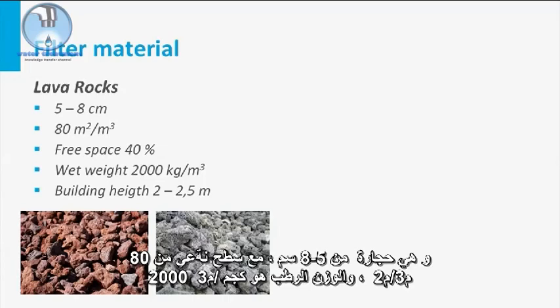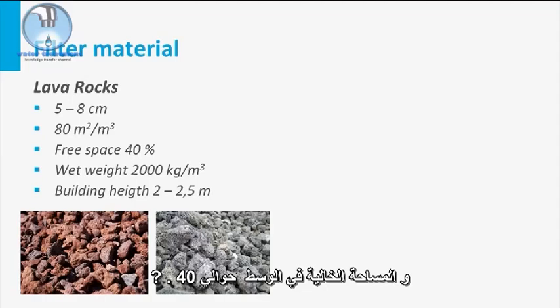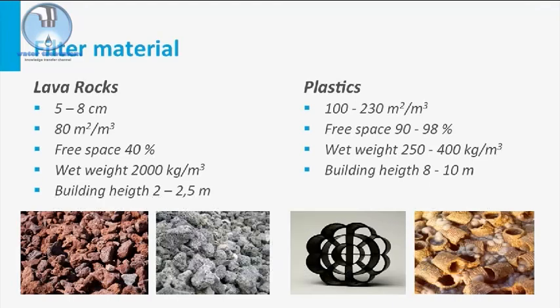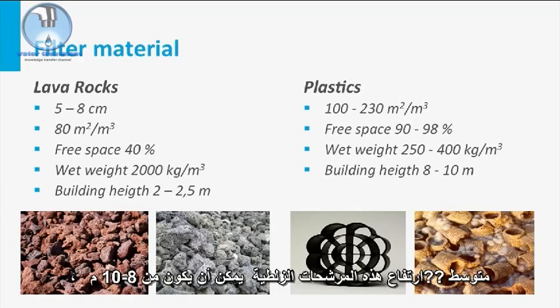Traditionally, lava rocks are used. These are 5 to 8 cm stones with a specific surface of 80 square meter per cubic meter. The wet weight is 2000 kg per cubic meter and the free space in the bed is about 40%. Trickling filters with this filling material have a height of 2 to 2.5 meters. High-rate trickling filters are filled with plastic with a specific surface of 100 to 230 square meter per cubic meter. The free space in the bed is 90 to 98% and the wet weight is only 250 to 400 kg per cubic meter, so the average height of such a trickling filter can be 8 to 10 meters.